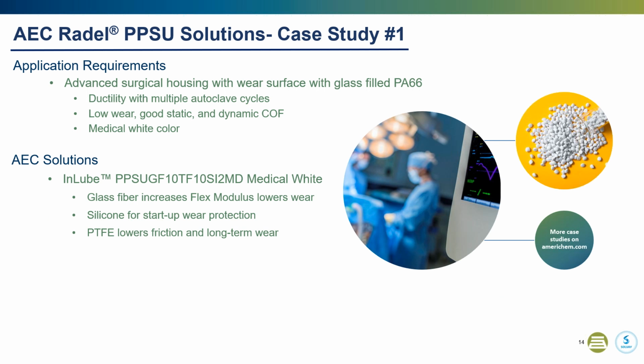At AEC, we've had a lot of success molding Radel in various housings. You know, amorphous materials mold with minimal warpage. Radel also provided the protection needed for the autoclave cycles. So easy choice to use Radel. We addressed the wear needs by adding 10% Teflon and 2% silicone. The 2% silicone is used for startup protection. It allows the needed time for break-in for the PTFE to bloom to the surface. The silicone then oxidizes away.